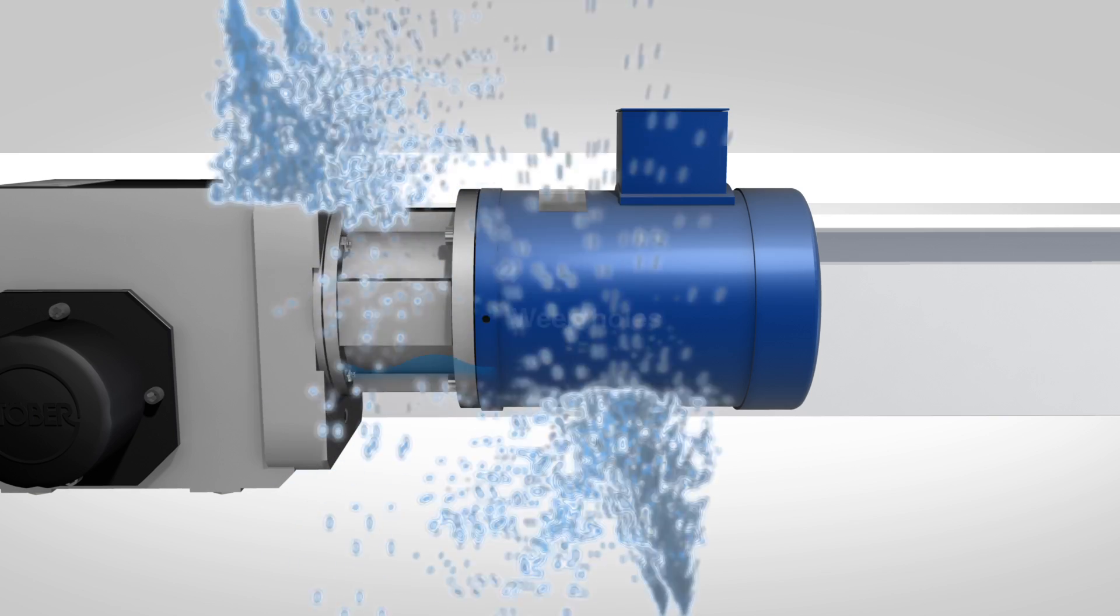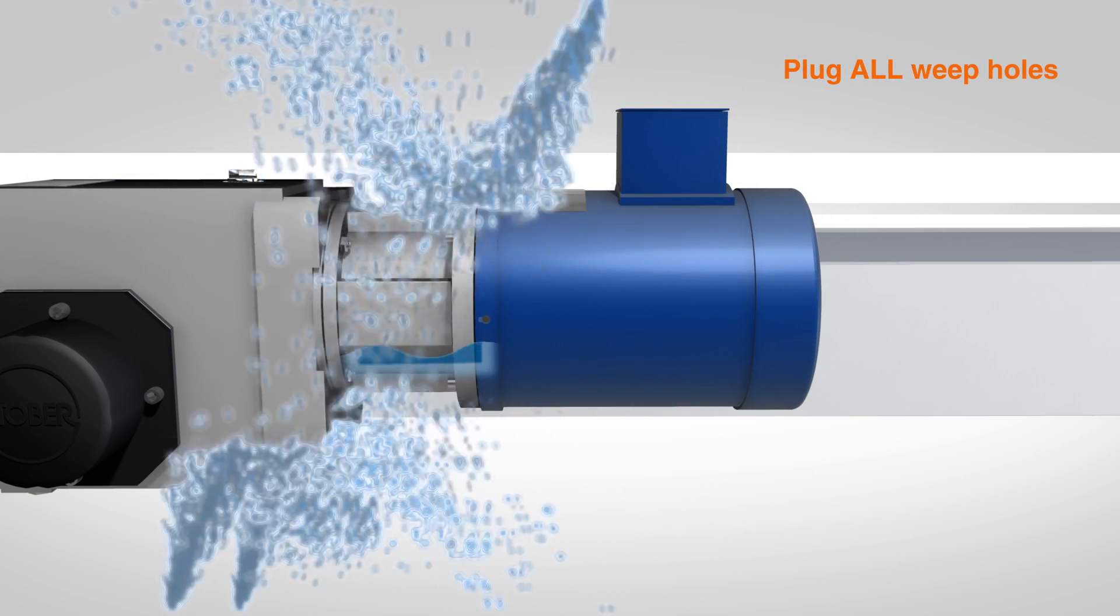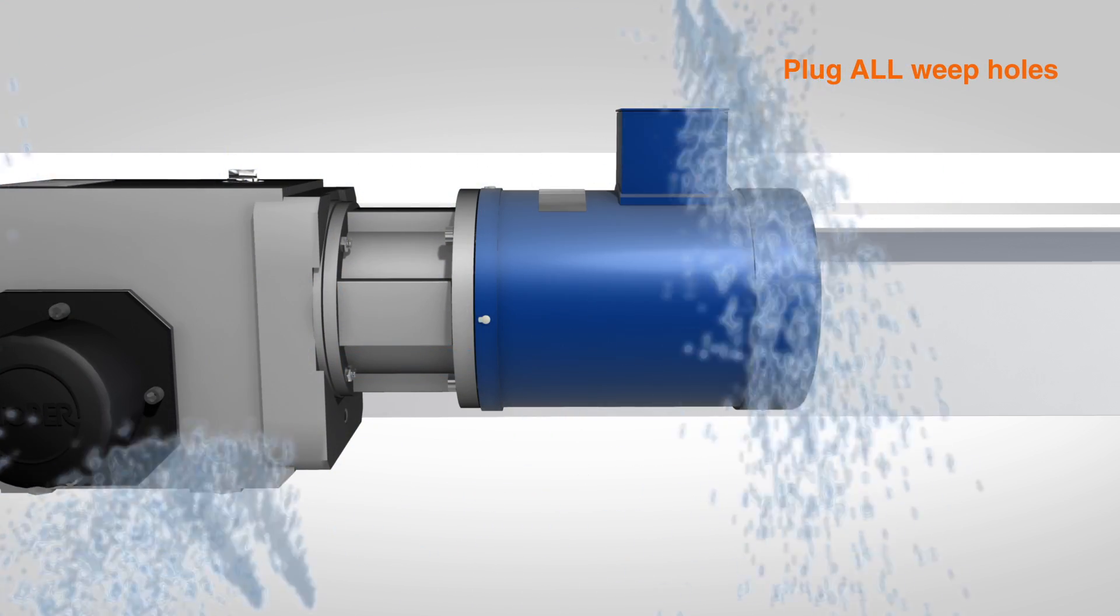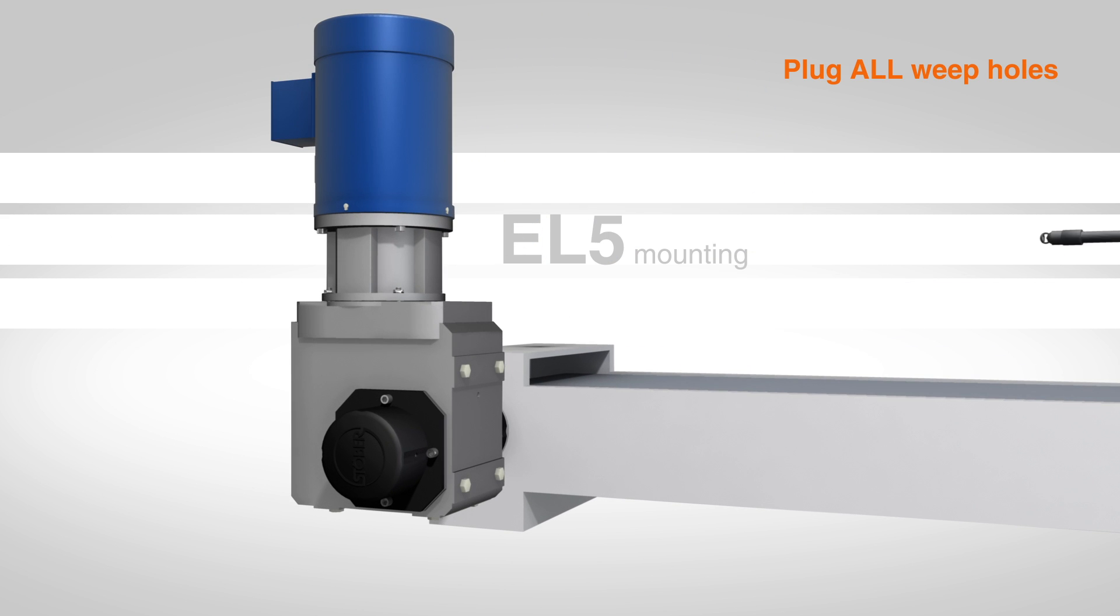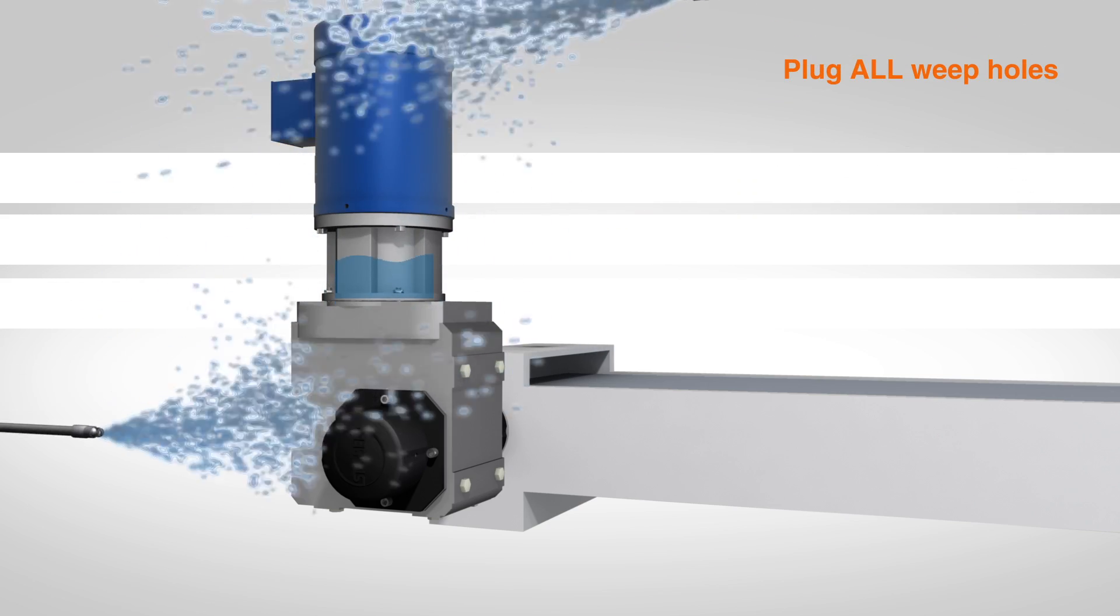Water or other material can enter the reducer through these weep holes and cause the motor adapter bearing to fail. This is important for all mounting positions, especially in EL5 mounting, as the motor adapter cavity can fill with water, significantly reducing gearbox reliability.